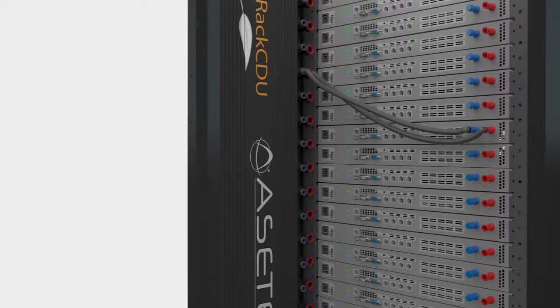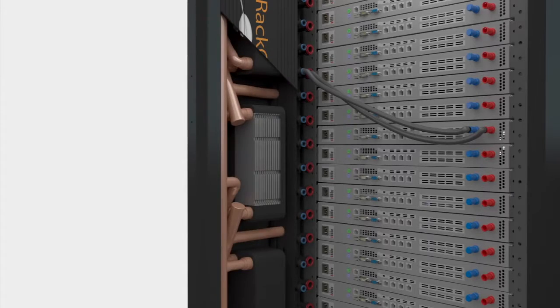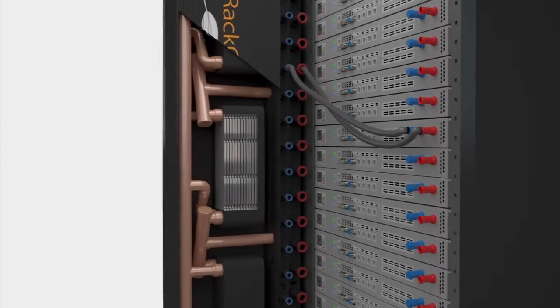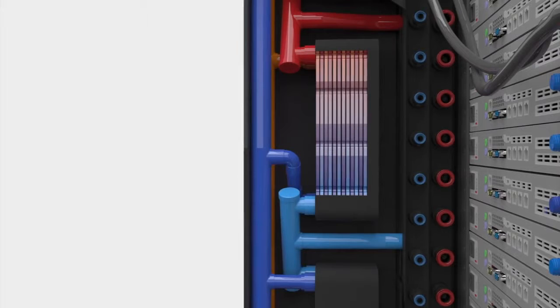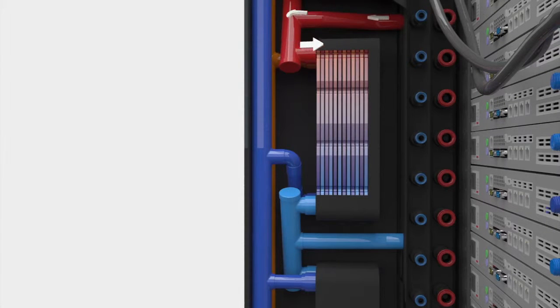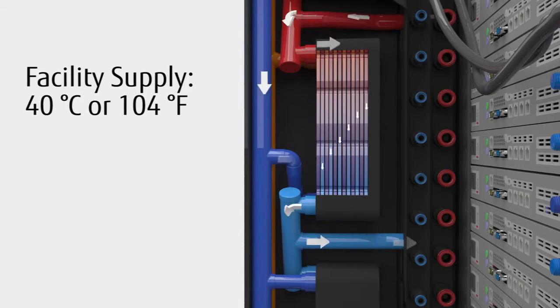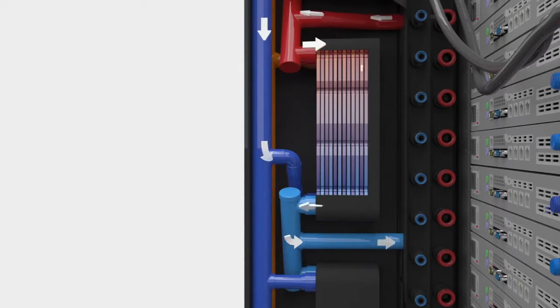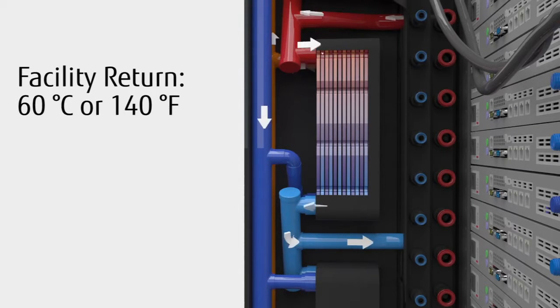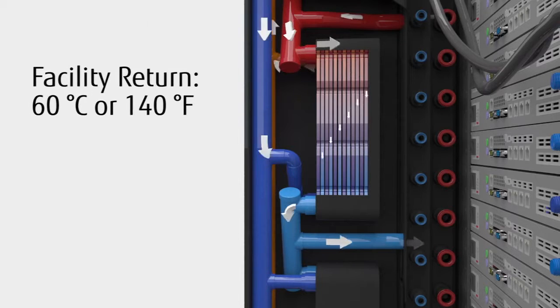The coolant distribution unit is attached to the back of the rack, where it does not occupy valuable rack height units. Heated coolant from the servers enters the CDU and is routed to liquid heat exchangers mounted inside. Now the heat is transferred to cooler facilities water, which can be as hot as 40 degrees Celsius. The liquid then exits the rack at a scorching 60 degrees Celsius.